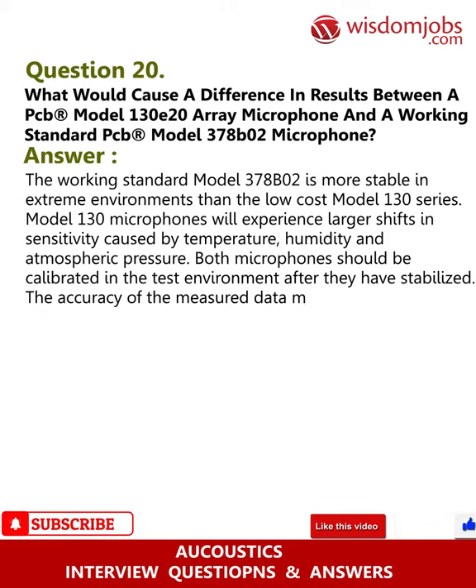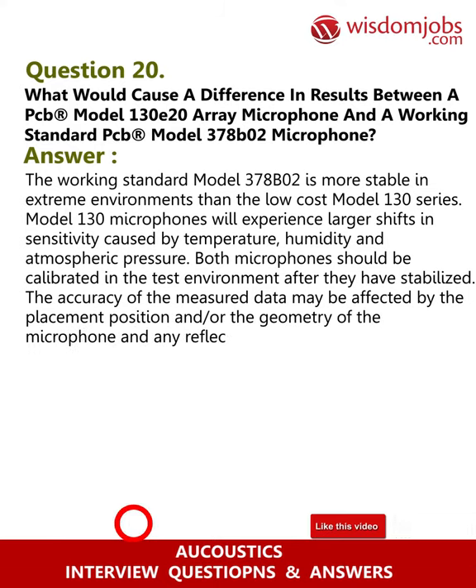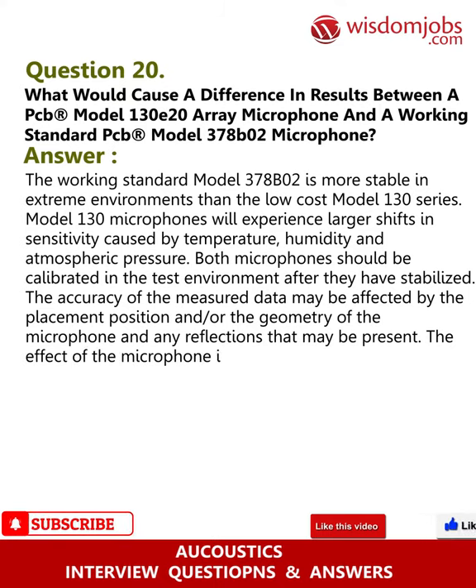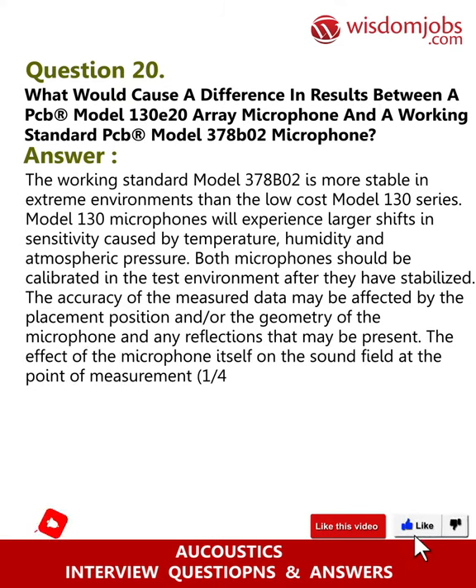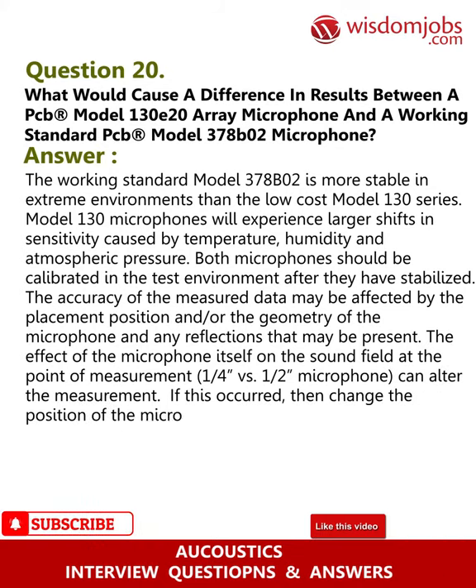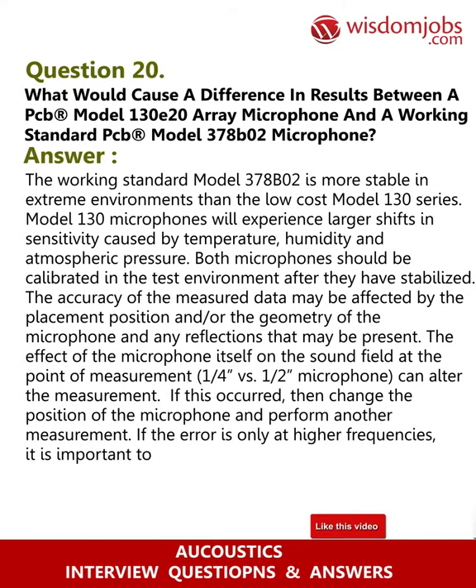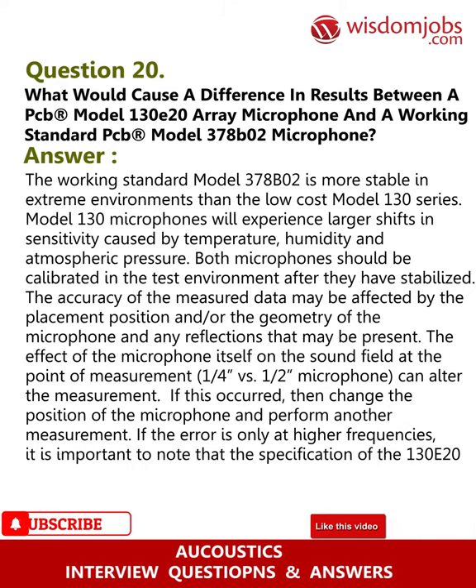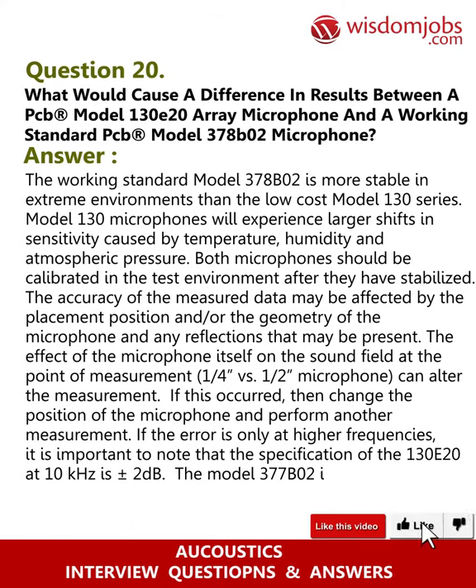The accuracy of the measured data may be affected by the placement position and geometry of the microphone and any reflections that may be present. The effect of the microphone itself on the sound field — one-quarter versus half-inch microphone — can alter the measurement. If this occurs, change the position of the microphone and perform another measurement. If the error is only at higher frequencies, note that the specification of the 130E20 at 10 kilohertz is plus or minus 2 decibels, while the 378B02 is flat to 20 kilohertz. Variations within tolerance may occur in specific instances.